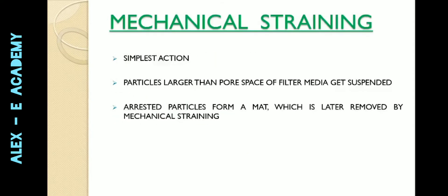Mechanical straining is one of the simplest actions. We have a filter media — the sand, not gravel — and water. Particles larger than the pore space of the filter media get suspended and arrested. Smaller particles may form a mat acting as a mechanical device. That is the first point of the theory of filtration.